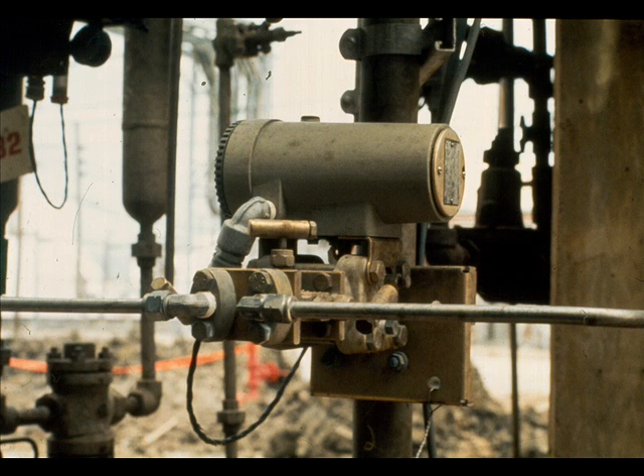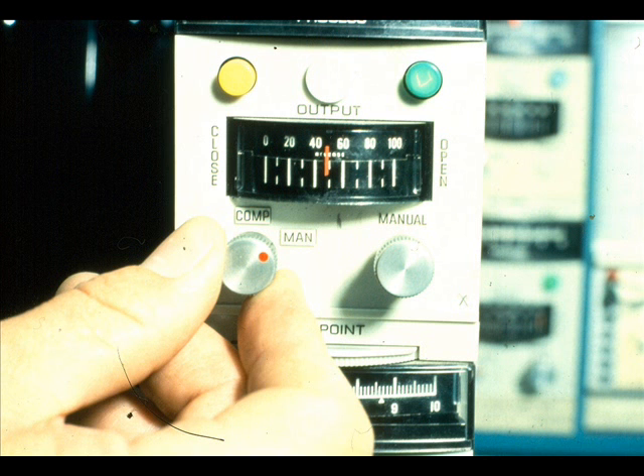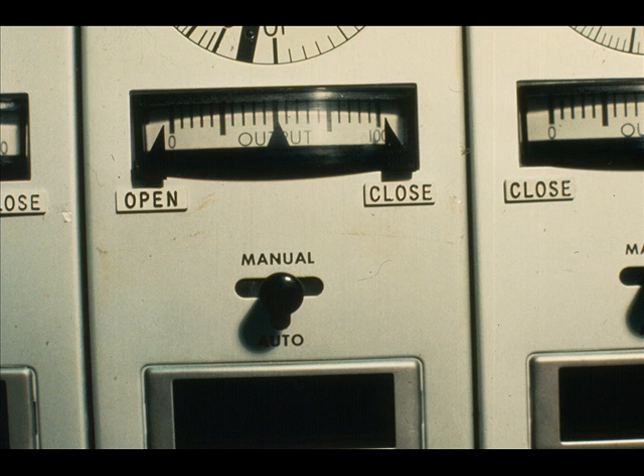This lesson will deal entirely with the transmitter itself and the transmission system. Impulse lines and associated problems have been covered elsewhere. Back to our low reading transmitter, if it is in a control loop, the control should be placed on manual.